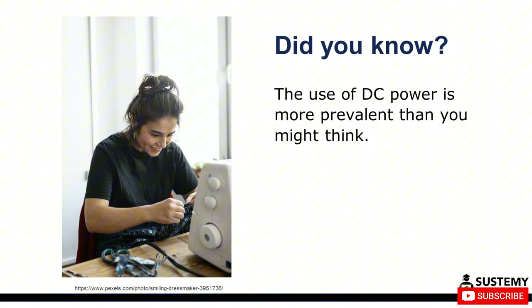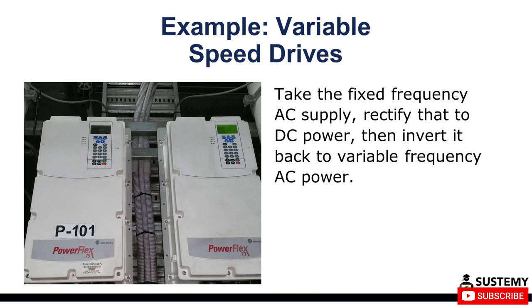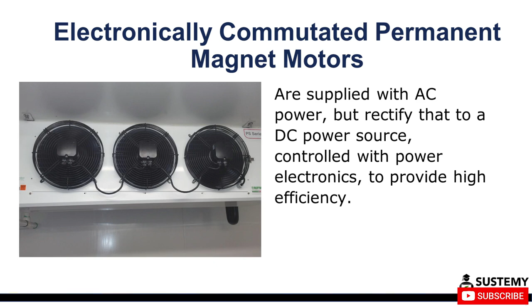Variable speed drives, otherwise known as variable frequency drives, VSDs or VFDs, often used with induction motors, take the fixed frequency AC supply, rectify that to DC power, then invert it back to a variable frequency AC power. Electronically commutated permanent magnet motors, or EC motors, used in applications such as plug fans, are supplied with AC power, but rectify that to a DC power source, which is then controlled with power electronics to provide high efficiency over a wide range of speeds. Your washing machine probably has a permanent magnet motor in it.